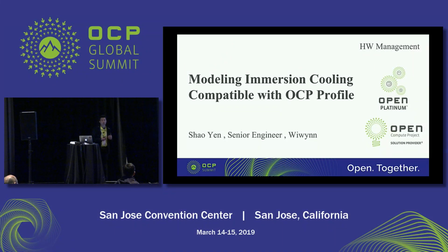Today, I'd like to talk about modeling immersion cooling compatible with OCP profile. We built a tank, and we use the OCP baseline hardware management profile as a blueprint. The goal is that the tank can be managed by existing DCIM software without any modifications.